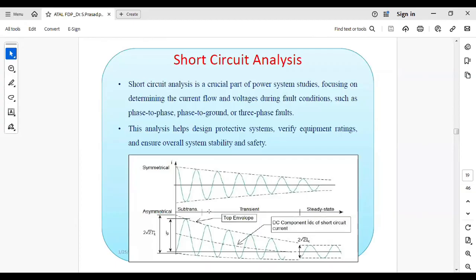This is also one of the most important analyses conducted by the consultant, to know what protecting devices we have considered in the plant, and whether all the ratings are okay or not. That we have to check. By conducting short circuit analysis, suppose a three-phase short circuit happens in the system, then how much maximum short circuit current will flow through a line, through the cable, through the power transformer, at the PV end. That we need to investigate.